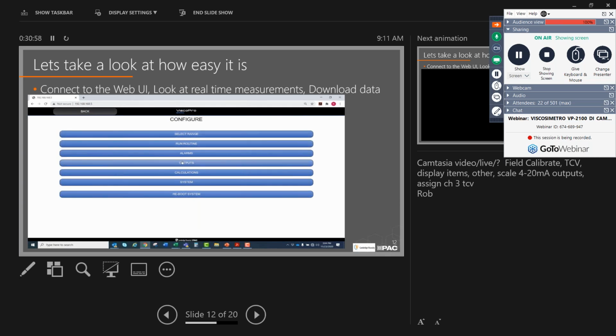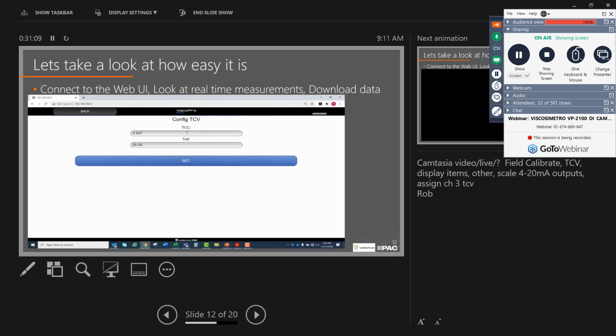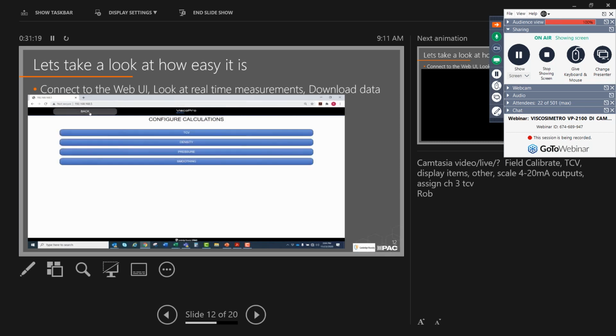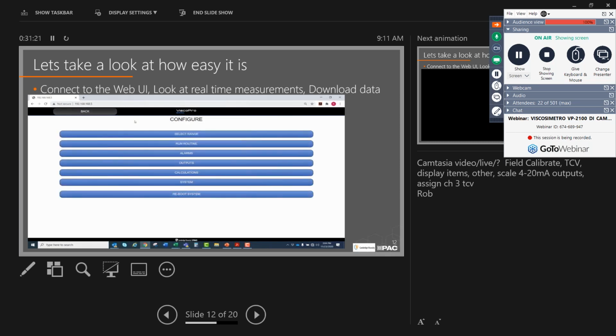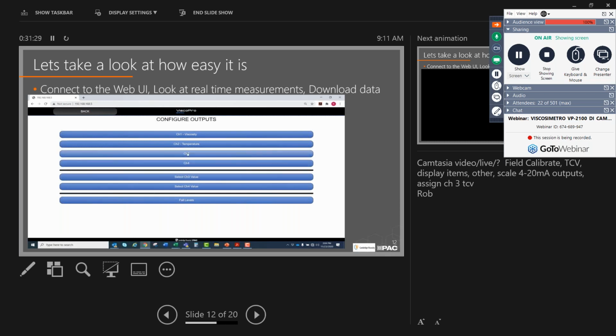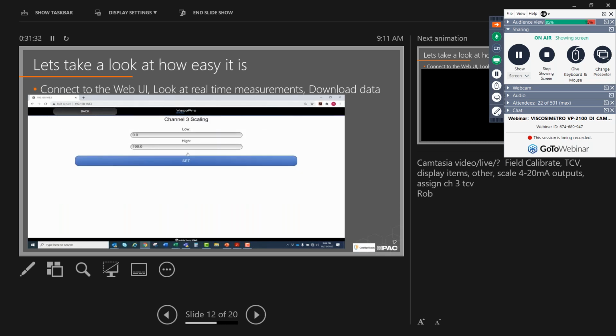The other thing that you could do as an example is if you wanted to enable your temperature compensated viscosity. So that would allow you to go in here and put in your temperature compensated coefficient as well as your reference temperature. One other feature that would be available is if you wanted to rescale your 4 to 20 milliamp outputs. Again, these have 4 to 20 milliamp outputs for viscosity, temperature, and other enabled items. So you could do it for temperature compensated viscosity.